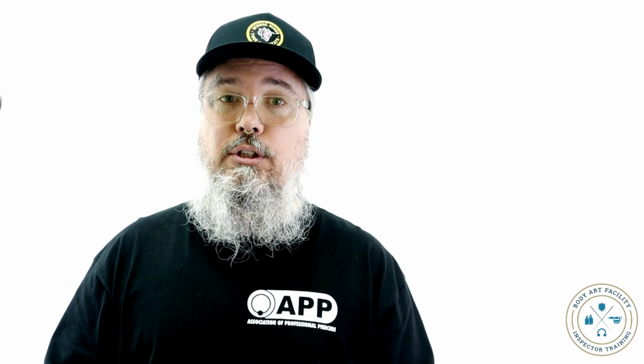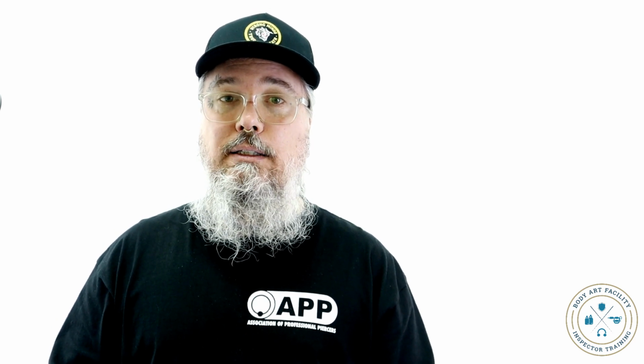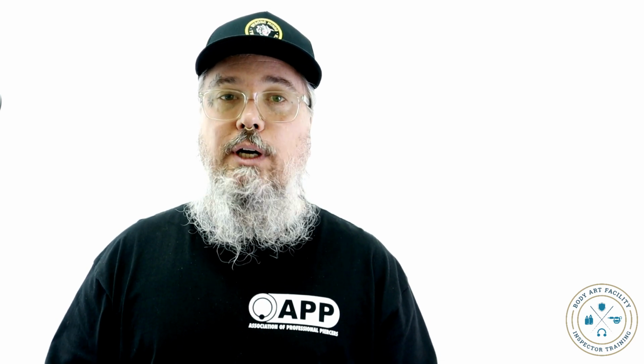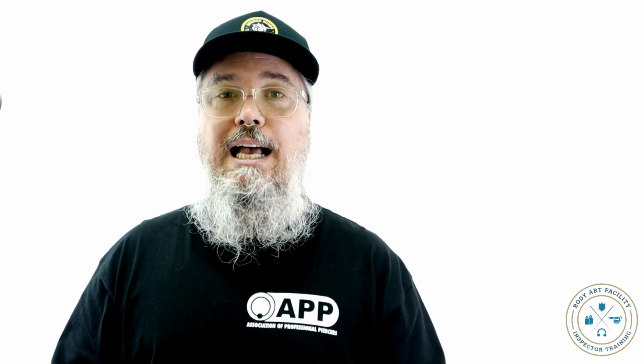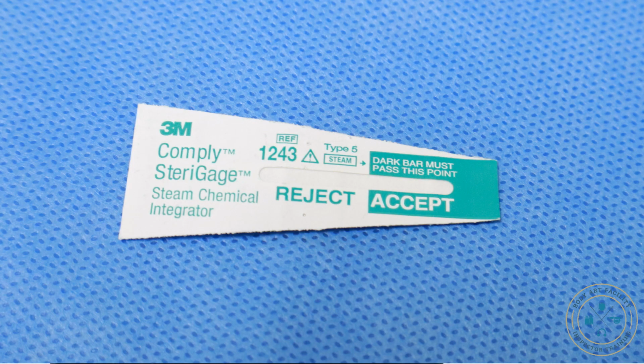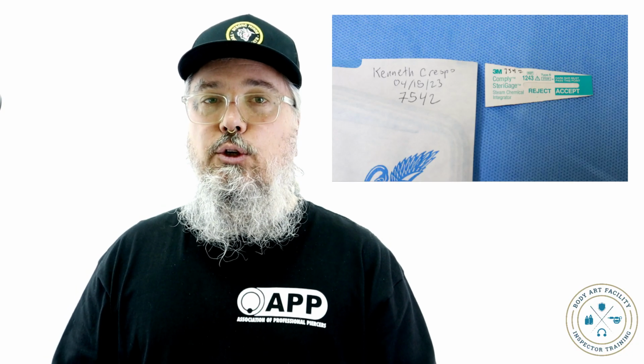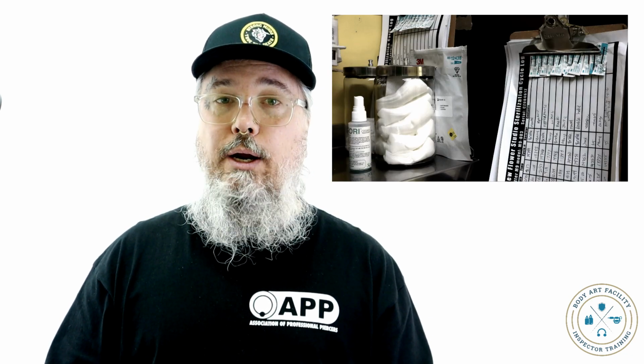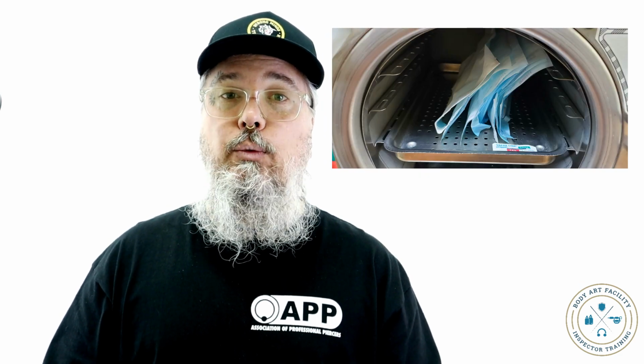However, these chemical indicators do not validate sterilization, which is why each autoclave cycle must include a Class 5 integrator. Integrators indicate that the parameters for sterilization, time, temperature, and pressure were achieved. These integrators can be labeled and kept with sterilization logs as part of the facility's record keeping. Integrators should be placed in the front of the autoclave near the door where they can be seen by anyone who opens it.